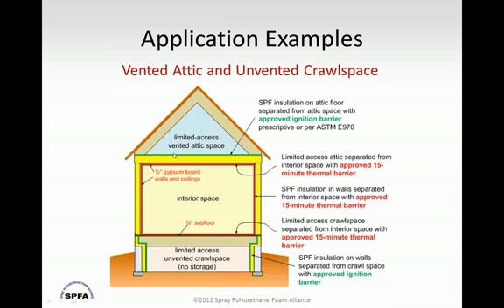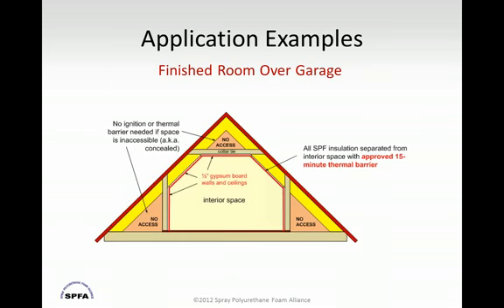And when you have this limited access space above, you still need to have an approved ignition barrier or a foam that's been approved to Appendix X without a coating as an ignition barrier per ASTM E970. Generally, what we're finding is that almost all foams will pass ASTM E970 without any additional intumescent coating or ignition barrier coating. So that's what we have for residential.